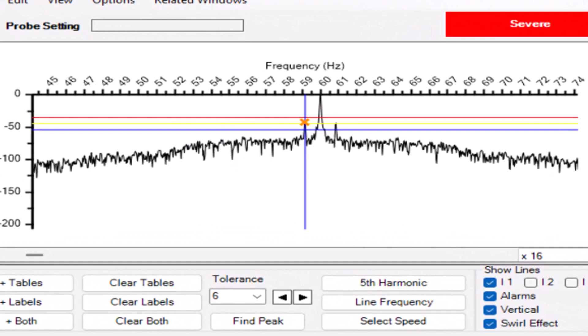Know the design of your rotor—is it a copper bar design? Is it spun cast aluminum? What's the speed of that motor? That's very key, it becomes critical for centrifugal force. And as you mentioned, open versus closed bar design can be critical. If it's closed bar and the bar's not going to fly out into the stator, you have some more time.